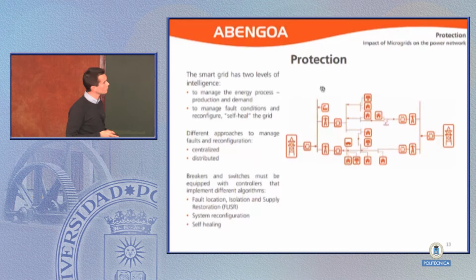After the fault occurs, the breaker that senses the overcurrent or the fault opens, leaving an area of the power system de-energized. Then a second algorithm must run, which is to try to reconnect as many subsections of the faulty section as possible by reconfiguring the network and opening the switches.